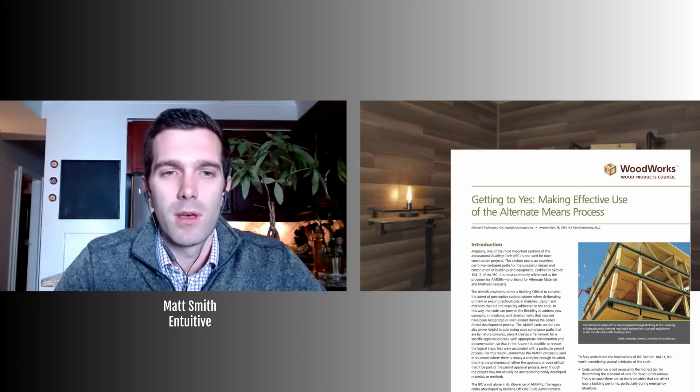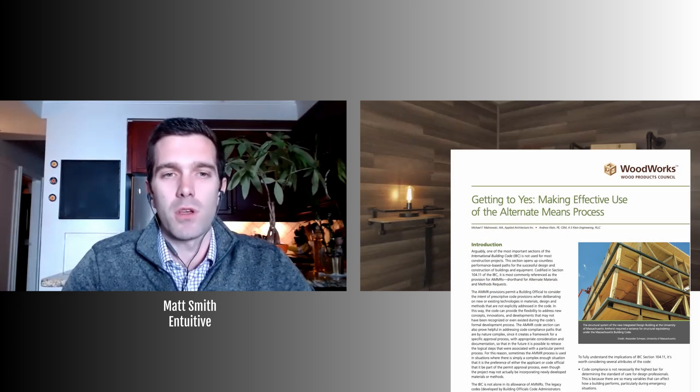When you're proving how a building performs, the criteria include timber exposure, size of building, occupancy, and more — really all of those. The actual process we go through is called the alternate materials and methods process, which is in the IBC. What the code asks us to do is: if you want to deviate from the code, you just have to prove your performance is the same as what would have been code compliant. So for examples like a larger area, a taller building, or more exposed timber, we'd be evaluating that specific timber building and showing that the level of safety or performance is the same as something that would have been code compliant.